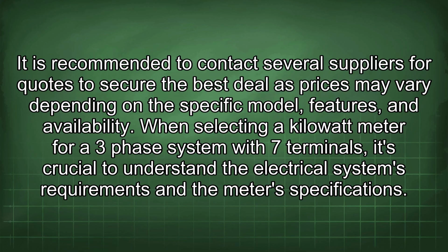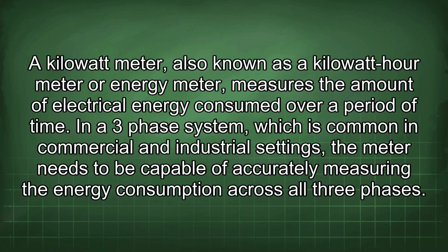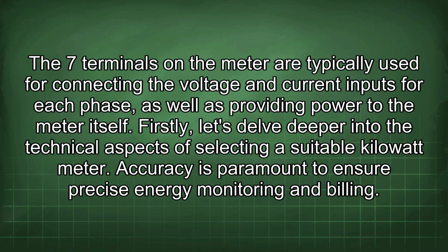When selecting a kilowatt meter for a 3-phase system with 7 terminals, it's crucial to understand the electrical system's requirements and the meter's specifications. A kilowatt meter, also known as a kilowatt-hour meter or energy meter, measures the amount of electrical energy consumed over a period of time. In a 3-phase system, which is common in commercial and industrial settings, the meter needs to be capable of accurately measuring the energy consumption across all 3 phases. The 7 terminals on the meter are typically used for connecting the voltage and current inputs for each phase, as well as providing power to the meter itself.